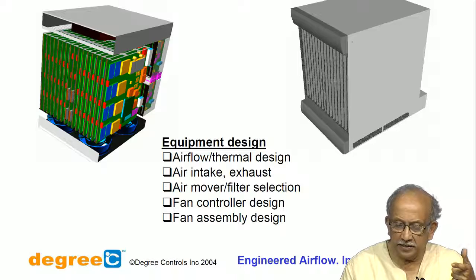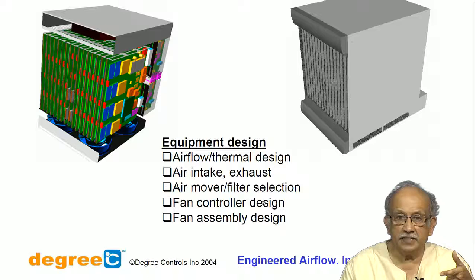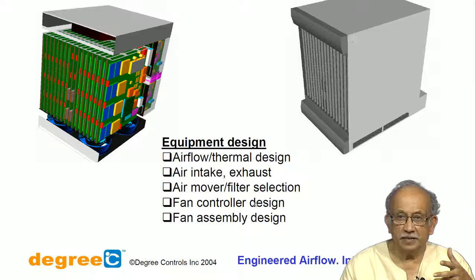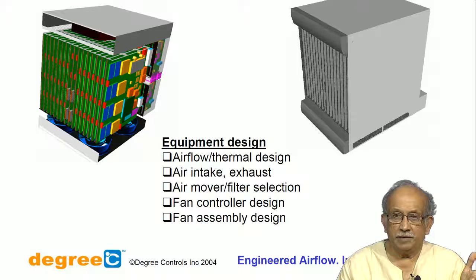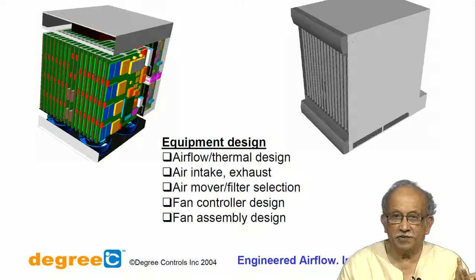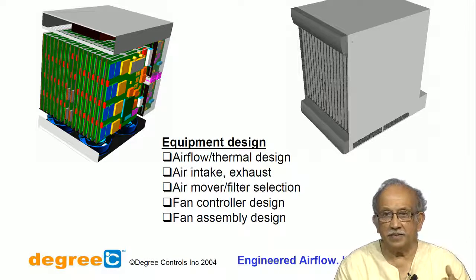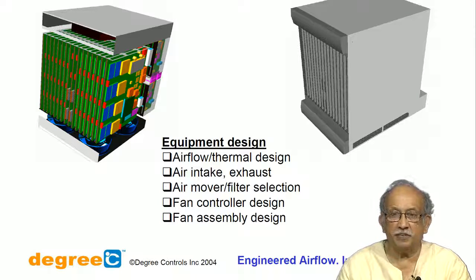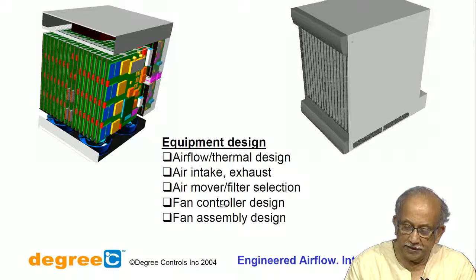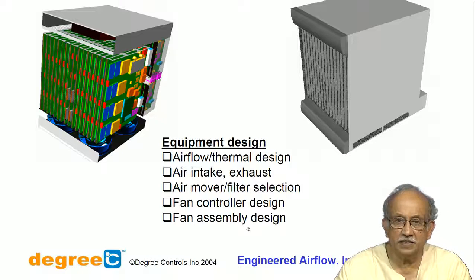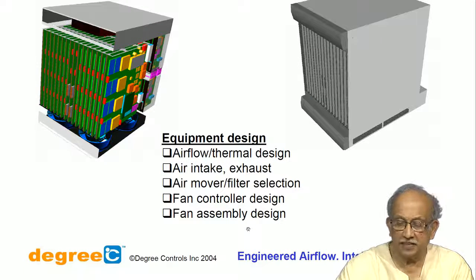This leads to the critically important fan controller design. You cannot afford to have a fan blowing continuously at full speed. Two problems arise: it will pick up dust, and fans are noisy — absolutely noisy. While a single fan in an anechoic test chamber may be barely audible, when several fans are placed together in a narrow working area, it becomes very, very loud. Related to this is the fan assembly design, involving different types of fans.